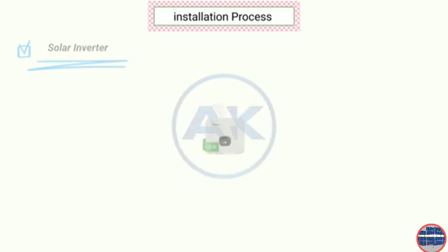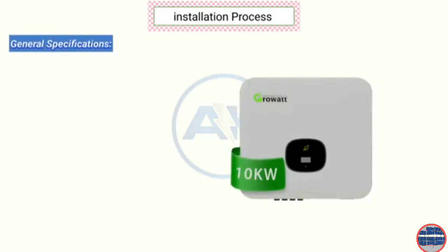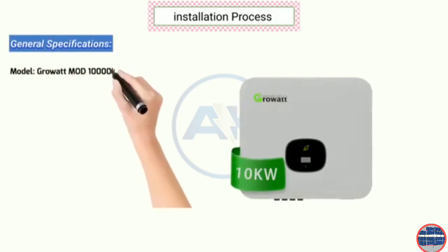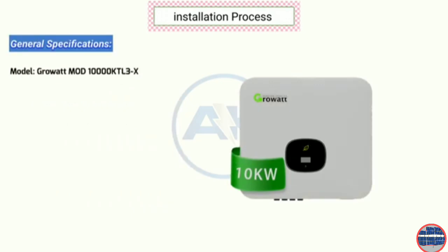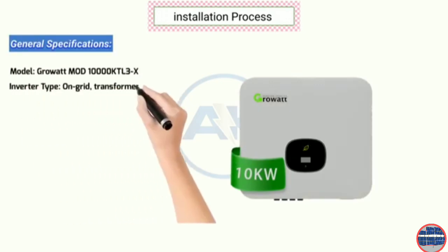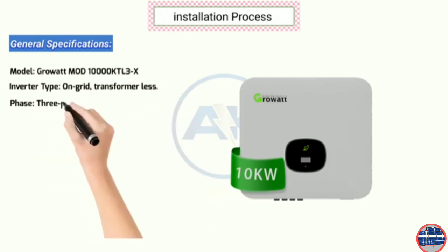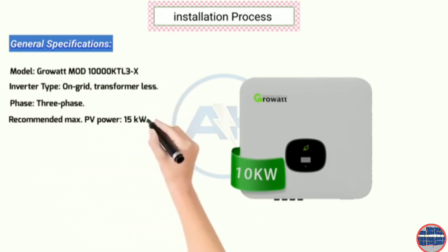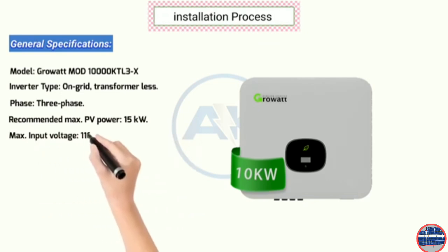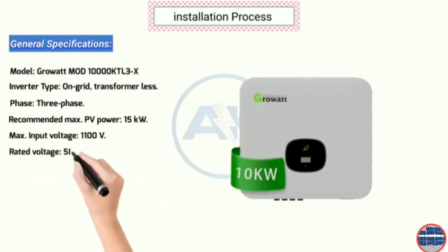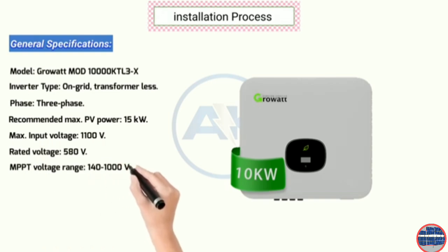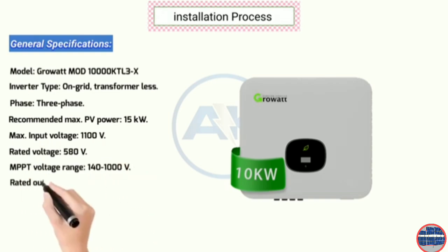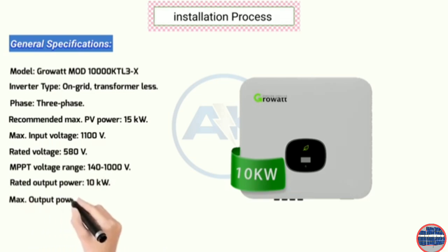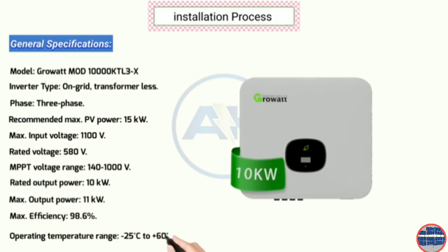Here are some of the key specifications. General specifications. Model Growatt MOD 10000 KTL3-X. Inverter type on-grid, transformer-less. Phase 3-phase. Recommended max PV power 15 kW max, input voltage 1100 V, rated voltage 580 V, MPPT voltage range 140 to 1000 V, rated output power 10 kW, max output power 11 kW, efficiency 98.6%, operating temperature range minus 25 degrees C to plus 60 degrees.